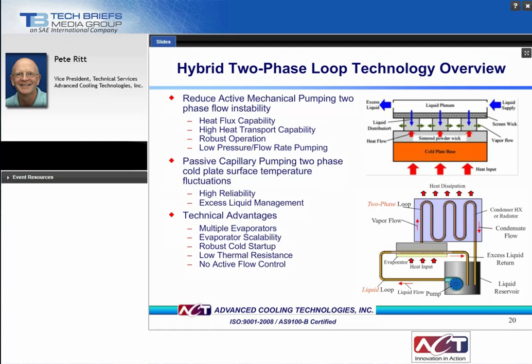Another issue that has been identified with pumped two-phase systems is the increased complexity with the addition of multiple evaporators. This is an issue especially with multiple high-powered IGBTs on the same base plate. One solution to the problem is to separate the functionality of the liquid pumping and then combine it with a passive capillary-driven two-phase loop. In this approach, which is diagrammed on the right, a mechanical pump supplies liquid to the evaporator and returns excess liquid to the reservoir. The pump only has to deal with the liquid and can therefore be more reliable and efficient.